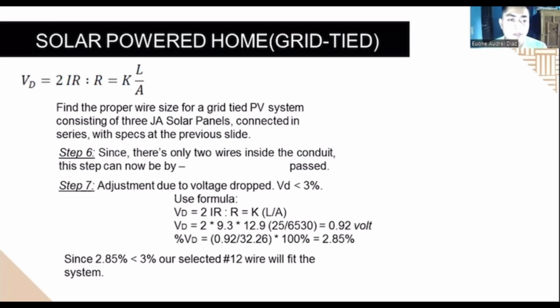VD is equal to 2IR, and R equals KL over A. Find the proper wire size for a grid-tied PV system consisting of three JA solar panels connected in series with specs at the previous slide. Step 6: since there are only 2 wires inside the conduit, this step can now be bypassed. Step 7, adjustment due to voltage drop. If less than 3%, use the formula for VD or the voltage drop.